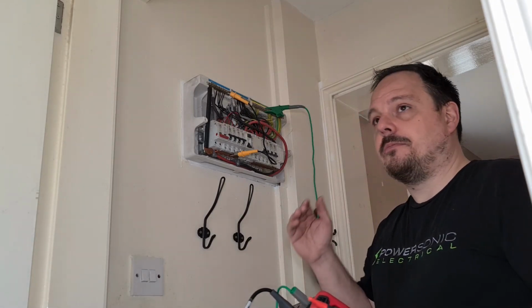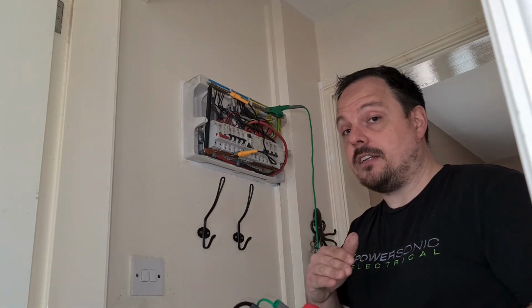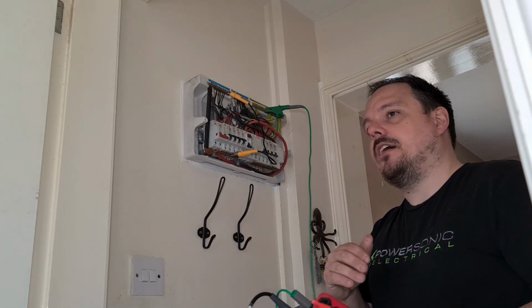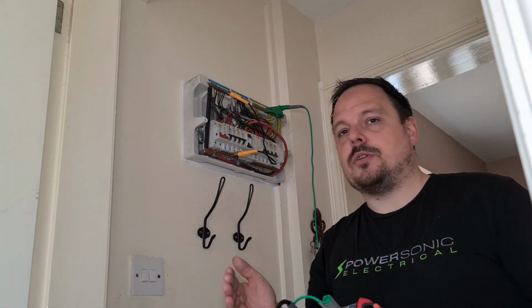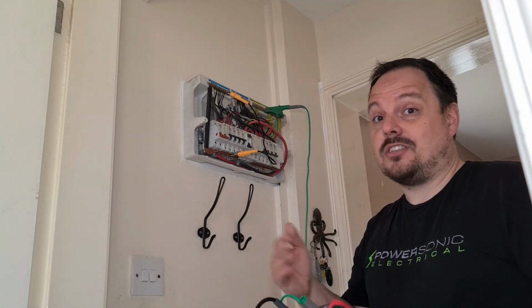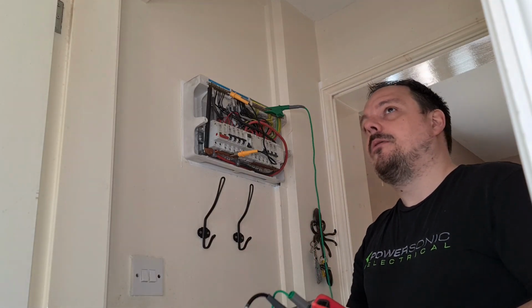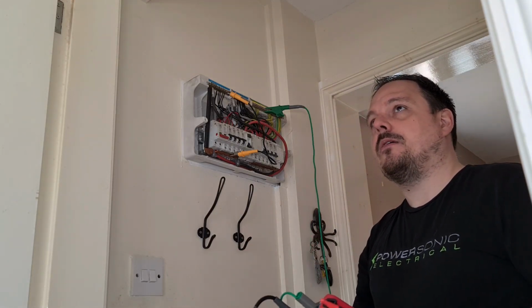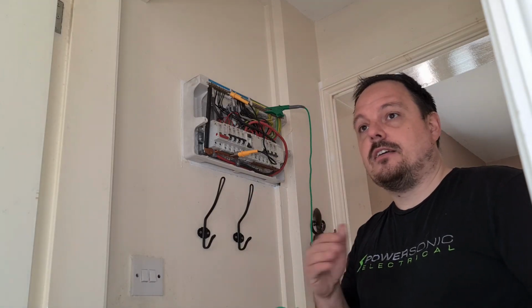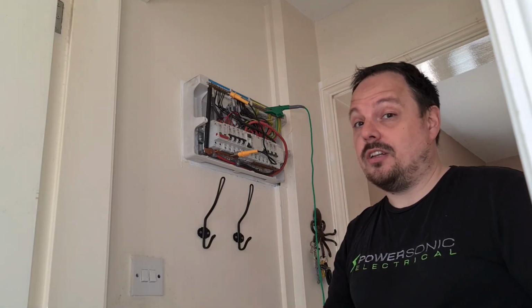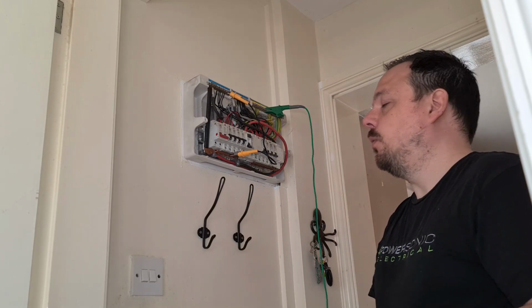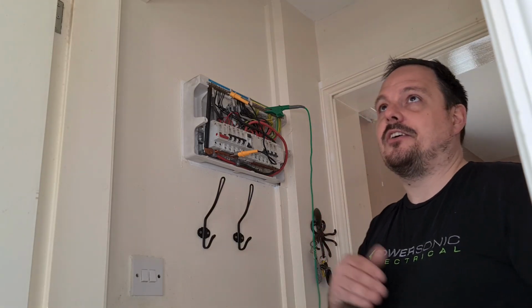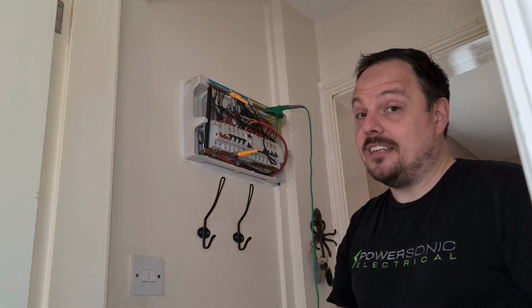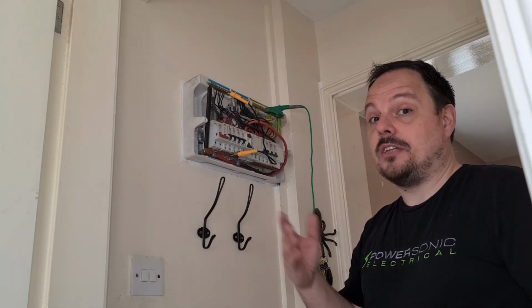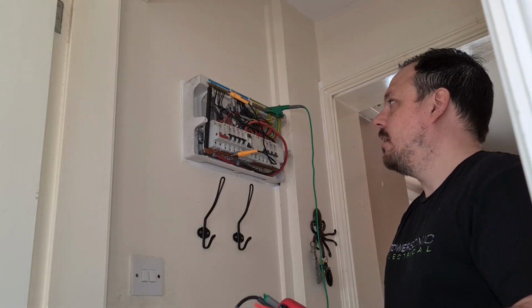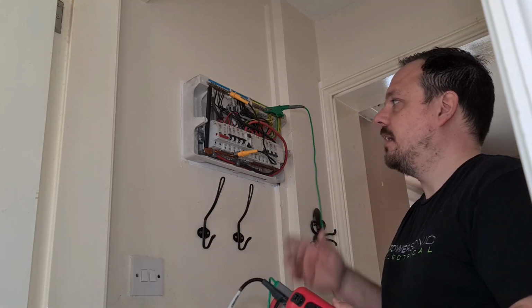You've got those minimum set values within the regulations to use as guidance, and if you just wanted to make a simple addition to a circuit, you'd know that circuit was acceptable to do so. But in this situation, where there's potential for that problem to worsen because there's been moisture ingress, you wouldn't want to be in the position of having had the whole building put back together and then need to take it apart again because the problem's got worse. So that's where I'm at with that - I'm going to do a bit more investigation on that one.